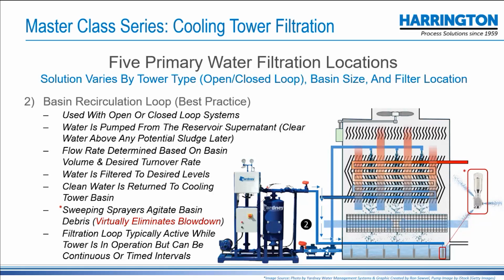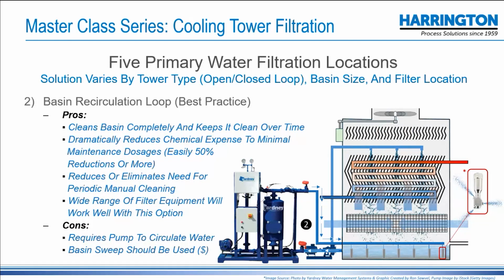Now, the other thing is, and it's a best practice, it's not mandatory, but it would be highly recommended, is that you put agitating sweep nozzles in a pipe frame within the basin so that they'll sweep back and forth and agitate the bottom of the basin. So if there is any sludge that builds up, it gets spun back into the water and removed by the filter. It keeps the basin completely clean, especially if you start with a clean basin. If you start with a clean basin, you will have absolutely no buildup over time. And I can say that with high confidence.